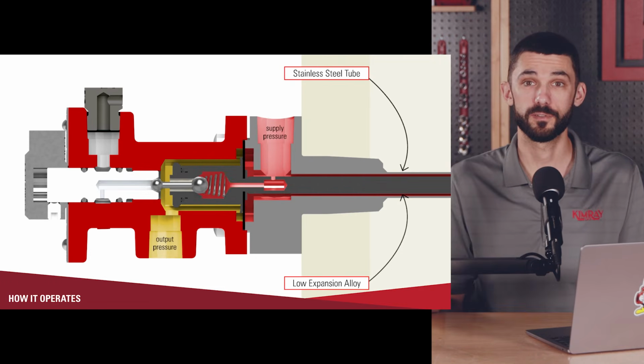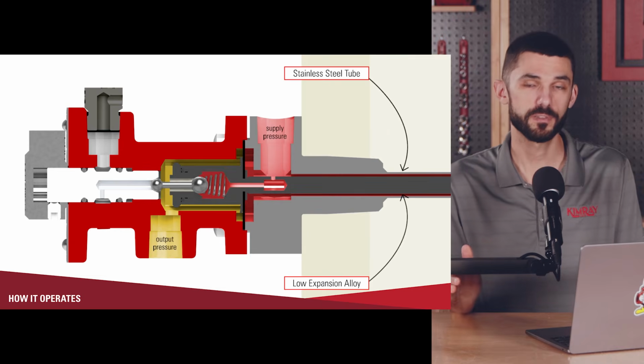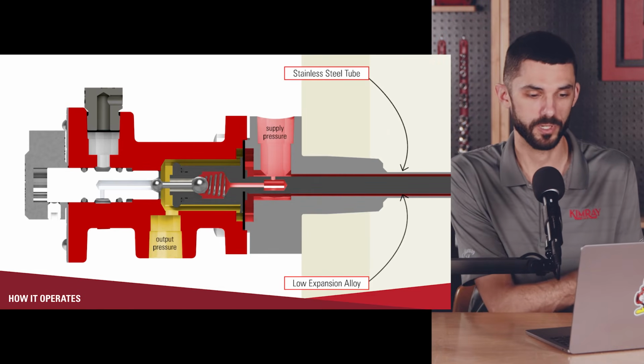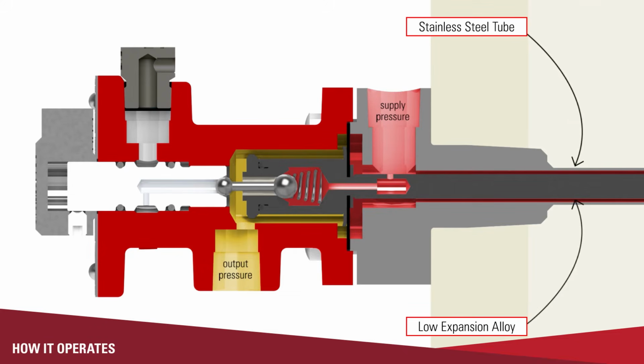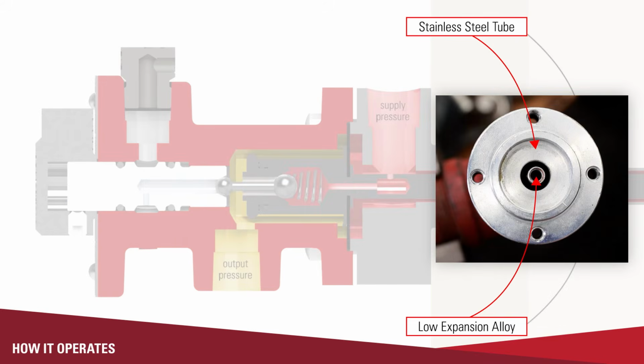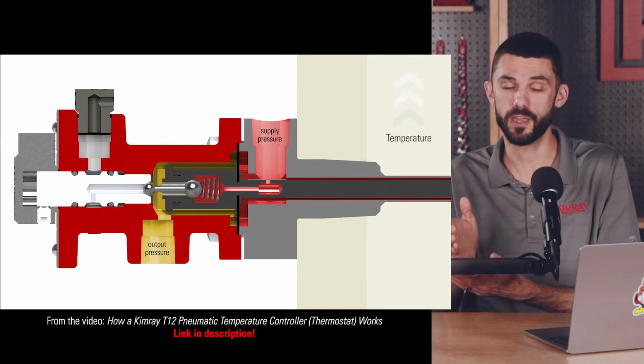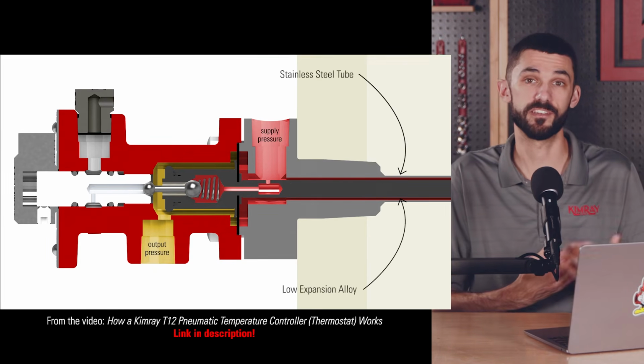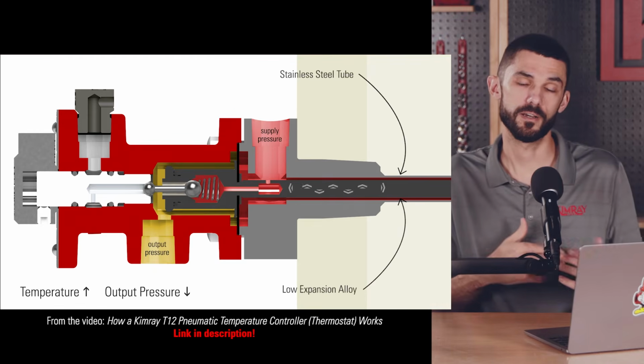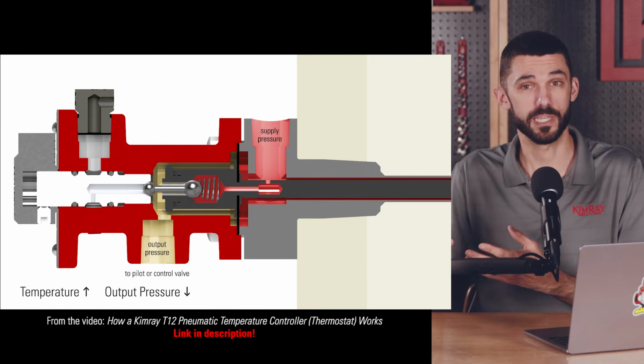All right, so I want to cover the operation of the T12, how it operates and functions. The stainless steel sleeve expands and contracts at a different rate than the low expansion alloy rod. So as temperature increases, the stainless steel jacket will expand and will pull the low expansion alloy rod, as well as the diaphragm assembly, closer into the vessel. That causes supply to be cut off and the path to vent to open. That would be an indirect acting mode.